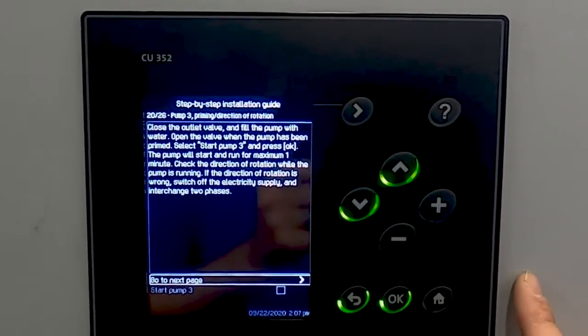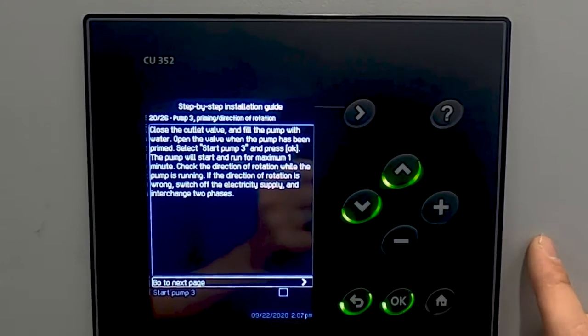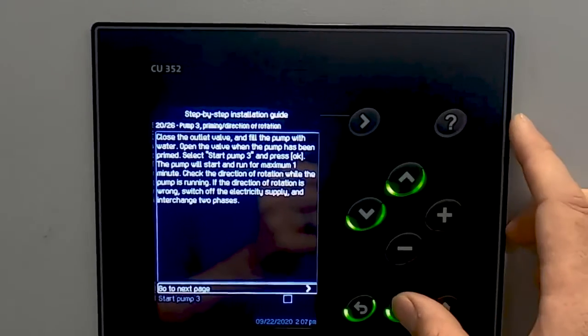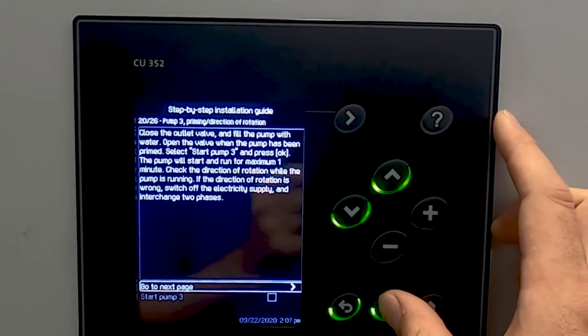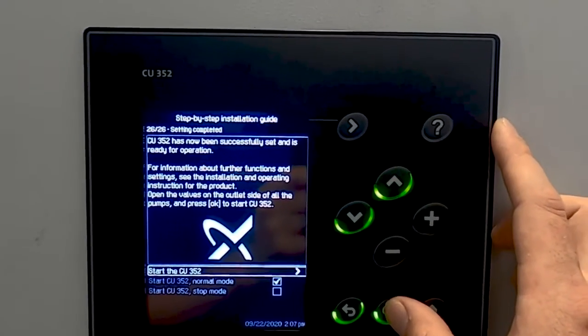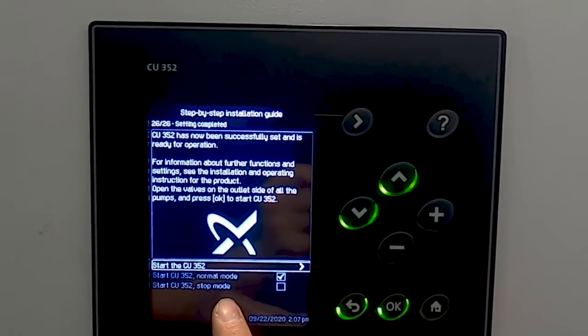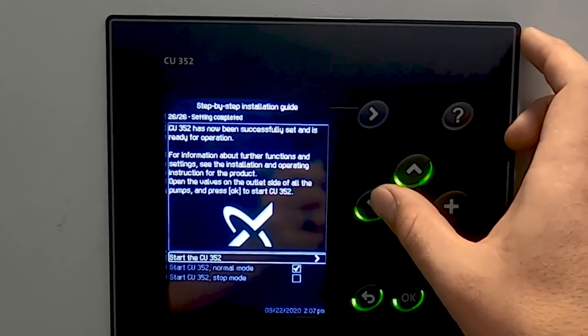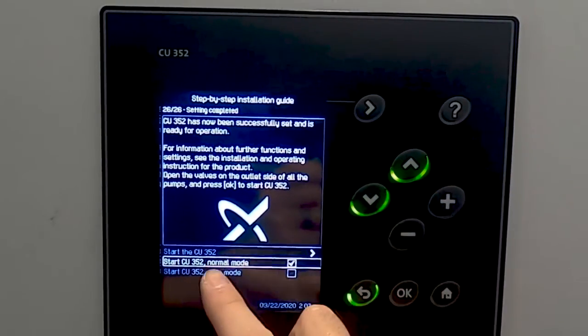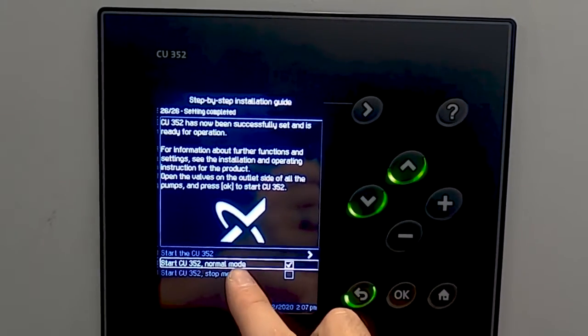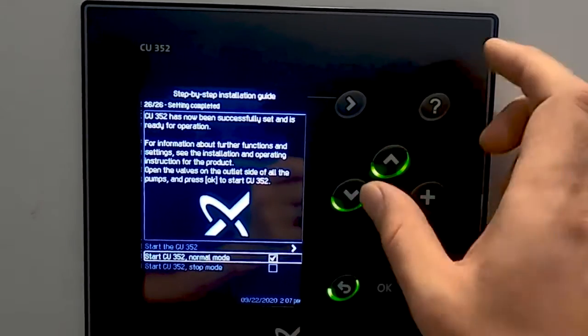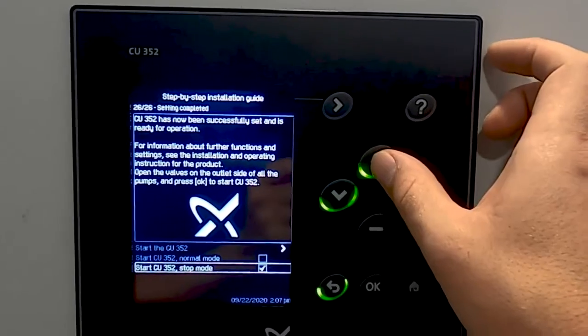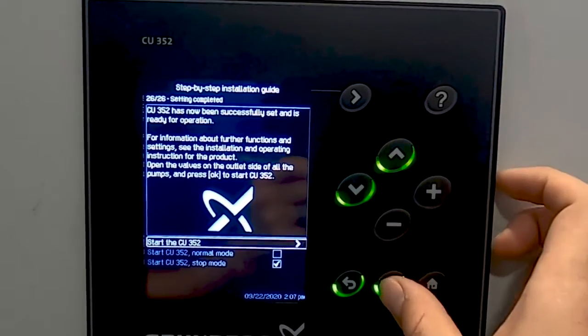Note there's also the option to check rotation. For our MLE motors, rotation does not need to be checked because they auto rotate. The final step in the startup guide is to actually start up the system and go to the main page. For ours, we're going to start in stop mode. You have the option of starting in normal, which would maintain the differential, or starting in stop mode, which will not allow the system to maintain the differential. I'm going to start ours in stop mode because there are a few other settings I'd like to show you.